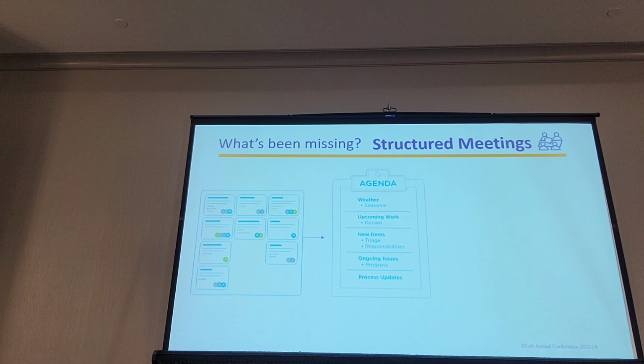Next, we're going to move to upcoming work. For example, if your buildings had building pressurization issues, and so you've got some overrides on the air handling units, and the facility team says, hey, we're going to be installing air curtains on Thursday night, just so you know. Well, then does that mean that we can take some of those overrides off the AHUs and see how they perform? Can we put them back in auto and continue troubleshooting this? Did that resolve our issue, or is there more digging that we need to do?